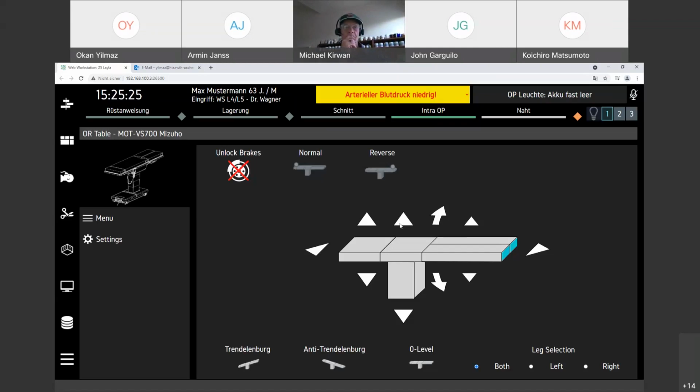And what we did, we translated the manufacturer protocol, partly using a microcontroller, into SDC. So if we want to drive the table up, we send the signal to the microcontroller, and the microcontroller translates it to SDC and sends the signal to the table.